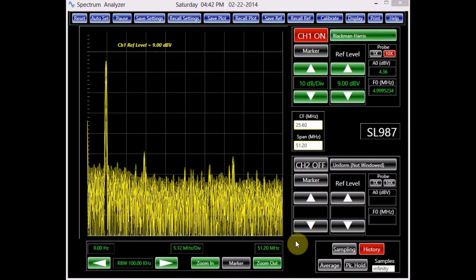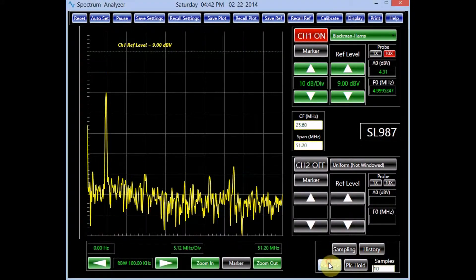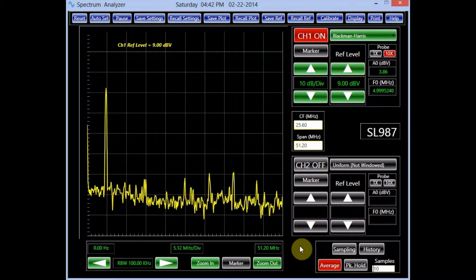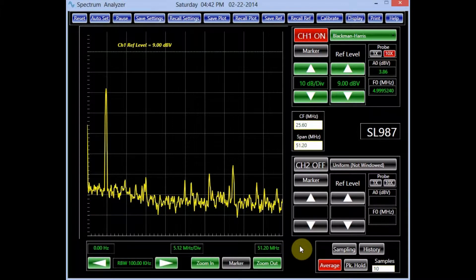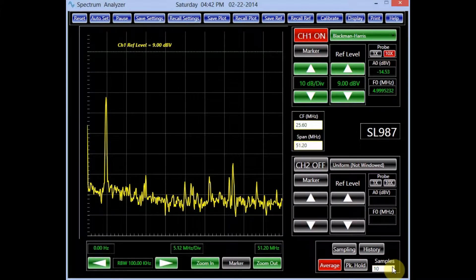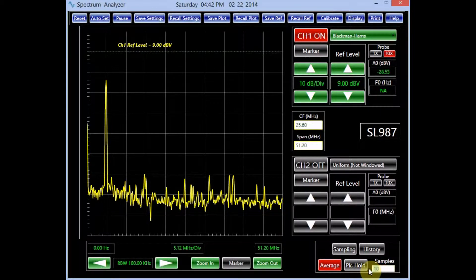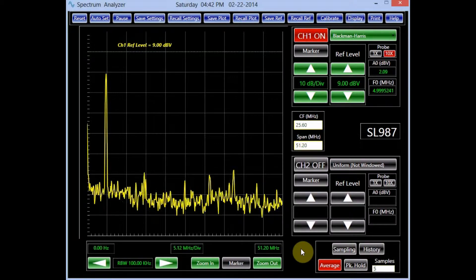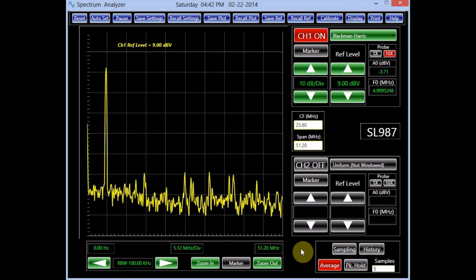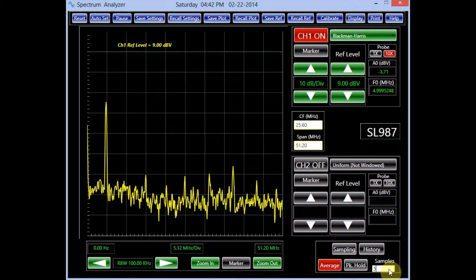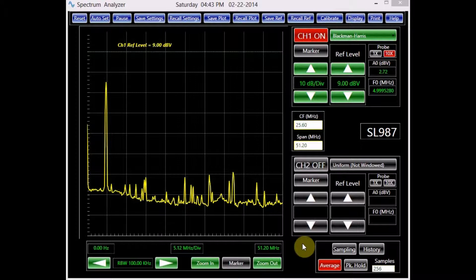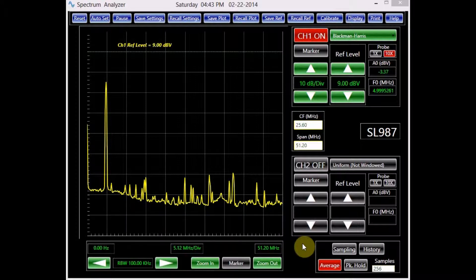In the average mode, the displayed signal is the average of a number of consecutively acquired data points. The number entered in the sample text box determines how many sets of data are averaged. This number can range from 1 to 256. The average mode is best suitable for repetitive signals. For this type of signals, it removes the uncorrelated noise and makes the signal stand out.